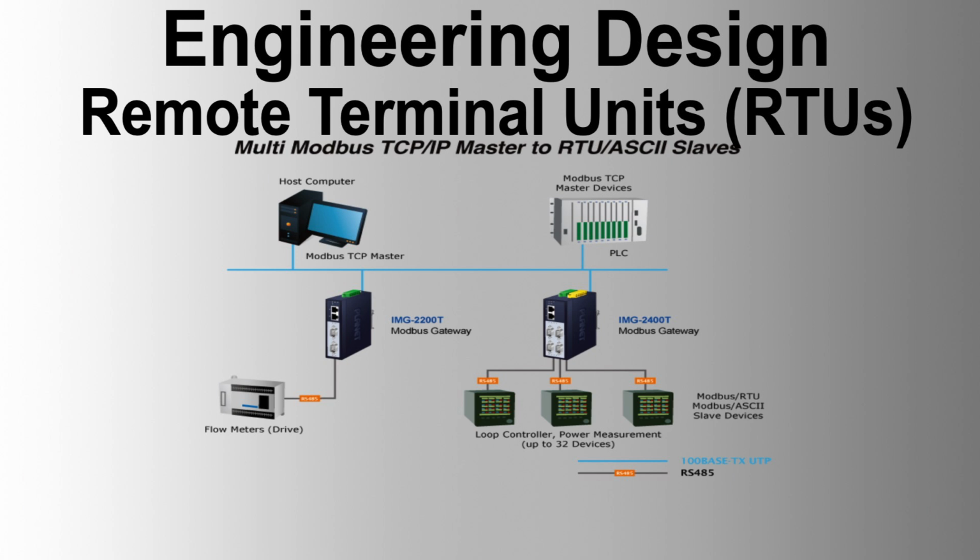Programming: RTU programming involves the use of a Windows-based interface for system configuration, logic programming, and database editing. This interface supports drag-and-drop features for function blocks, password-protected access control, data import-export in ASCII, Excel, and Access formats, online and offline modifications without system disruption, and ladder logic, text, and function block formats compliant with IEC 61131-3.